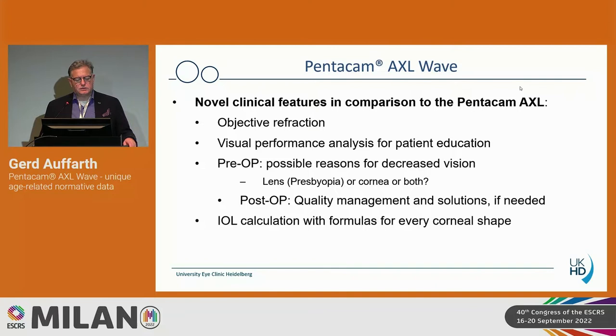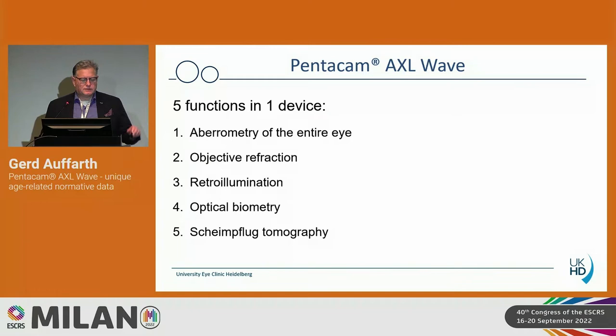The novel features in the Wave include objective refraction and visual performance analysis, and the IOL calculation is upgraded and updated for every corneal shape. The Pentacam now stands for five functions: aberrometry of the entire eye, objective refraction, retroillumination, optical biometry, and the basic Scheimpflug tomography where it all started.